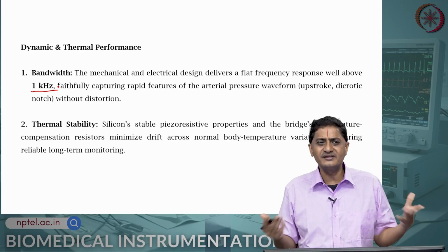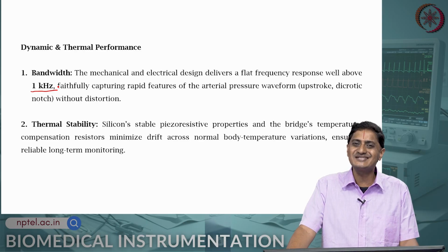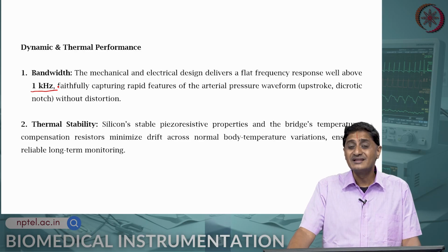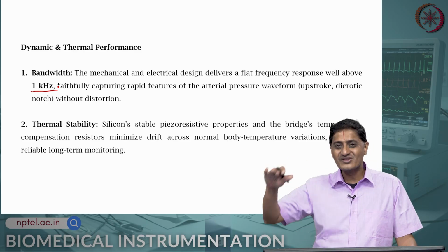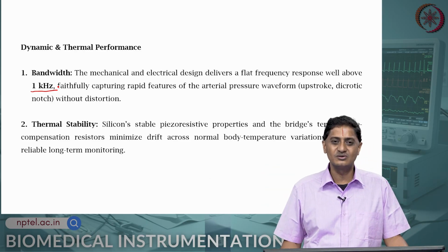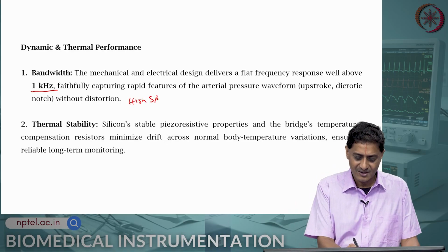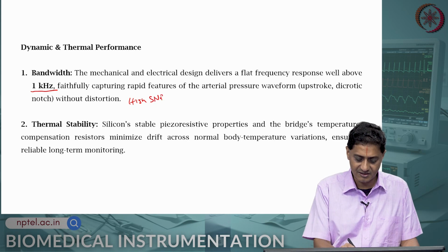But the point is that 1 kilohertz faithfully captures extremely fast changes in the arterial pressure waveform, thus providing a relatively accurate and high fidelity measure of the waveform without distortion. So, these are high SNR and high fidelity measurements.